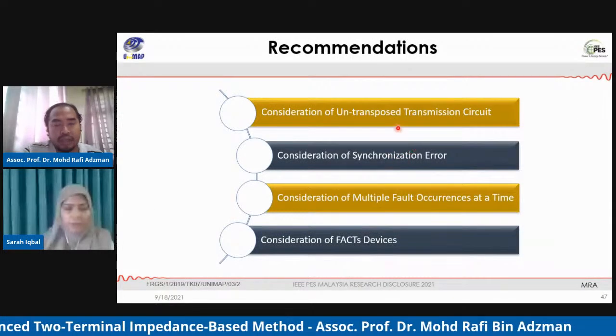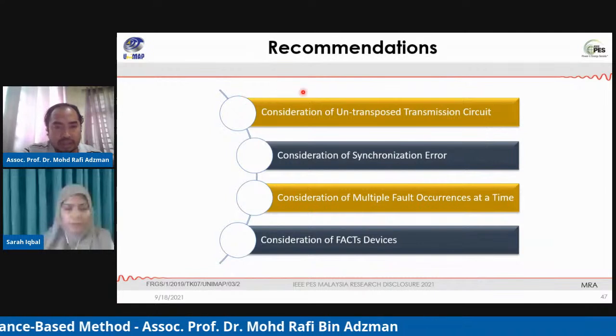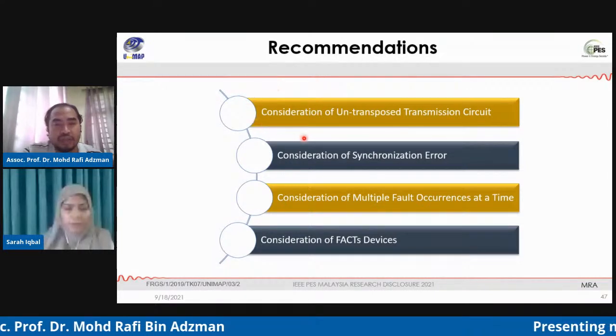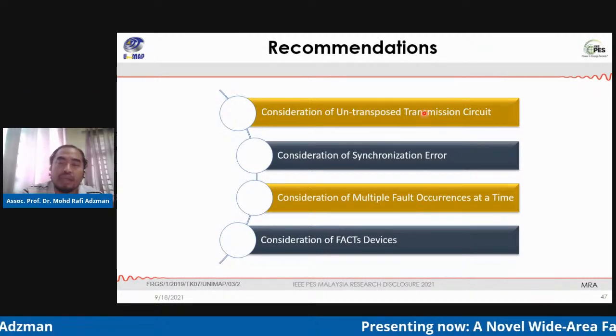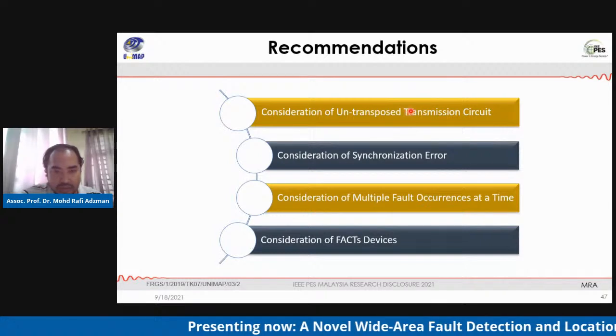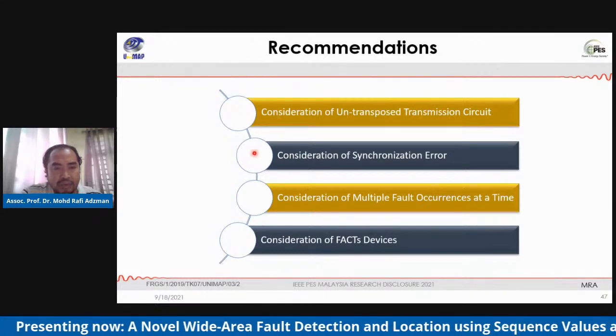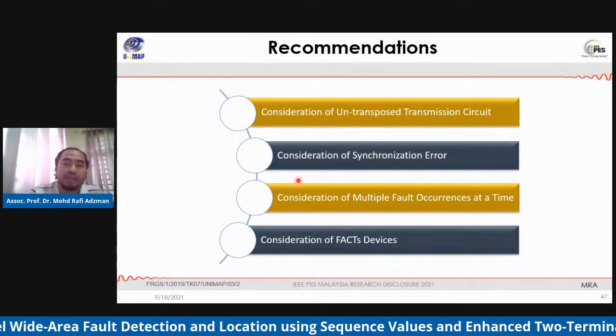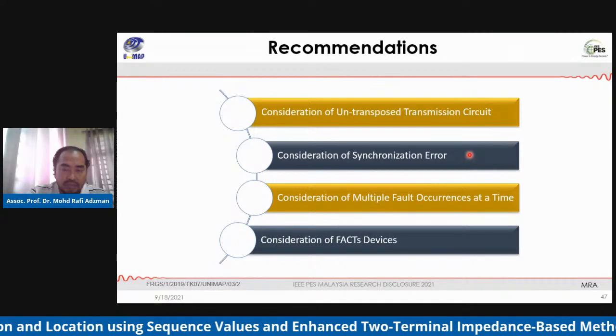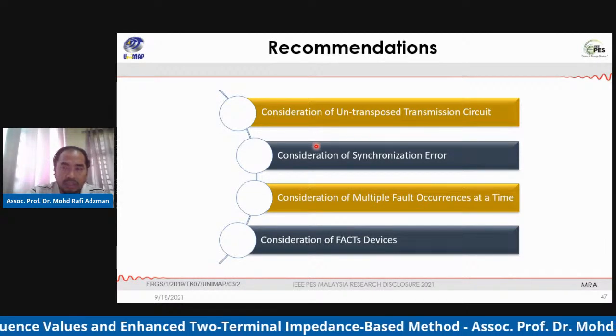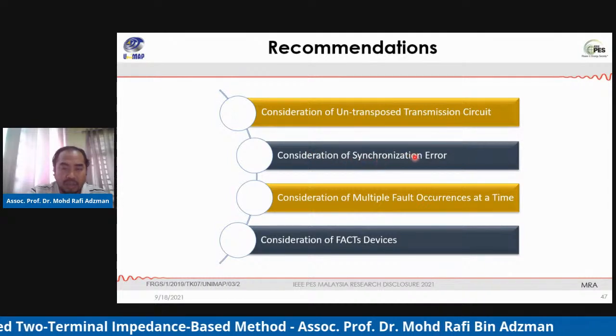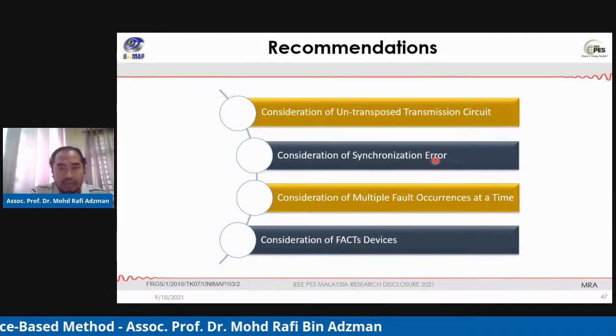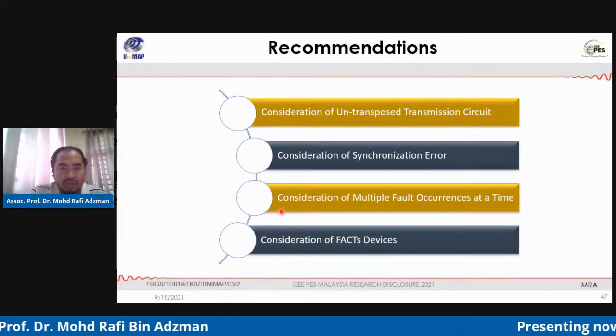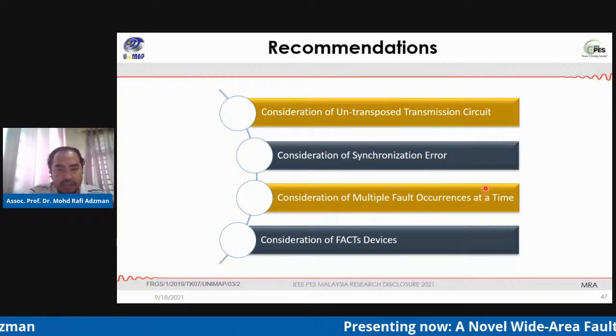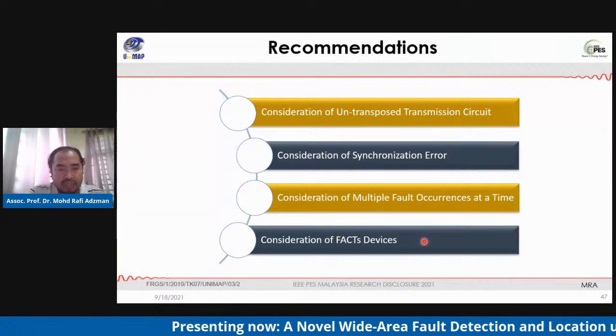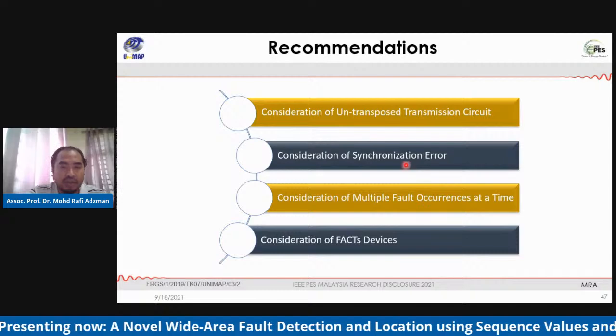There are some recommendations from this work. For the next step, we have to look at the consideration of the untransposed transmission circuit, because in the line sometimes we have transposed and also untransposed transmission circuits. We also have to consider the synchronization error when we do the calculation for fault location algorithms, because sometimes we have miscommunications and some data will not be received accurately. We also have to consider multiple fault occurrences at one time. And last but not least, we have to consider FACTS devices for this kind of work.